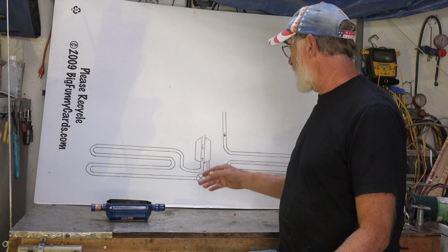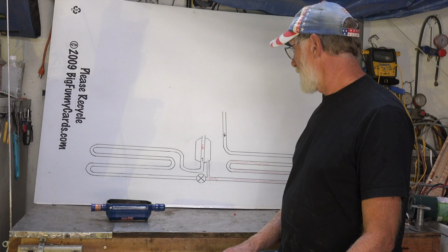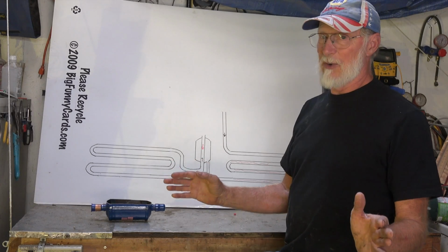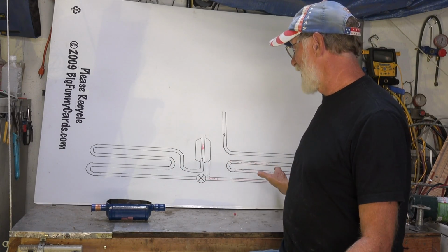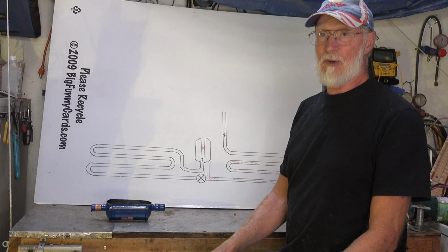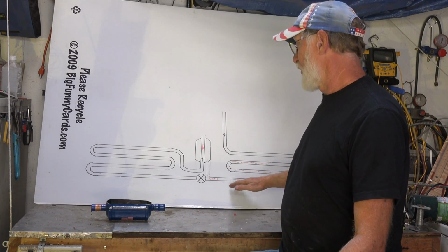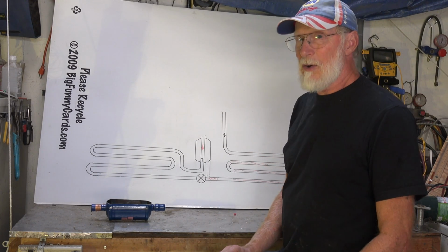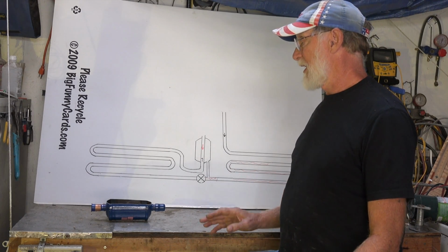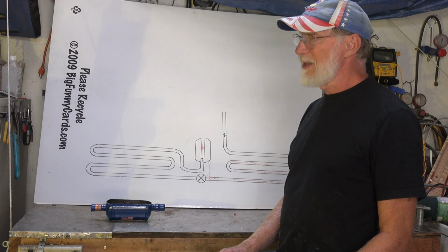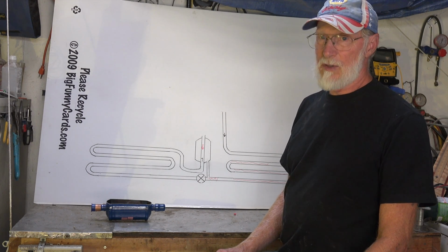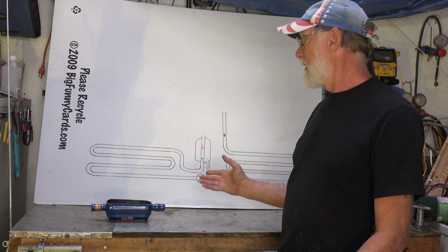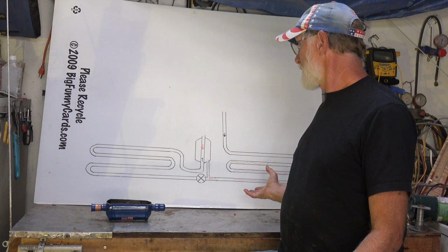I suppose if I put this on a refrigeration system, it wouldn't work. The receiver works. All I can see is this thing filling up full of refrigerant regardless of load, so I don't think it could make a difference. But that's a difference between the two. I would not call the compensator a liquid line receiver because it really isn't. It really doesn't work that way. Anyway, I hope I've explained this well. That's it on this one.